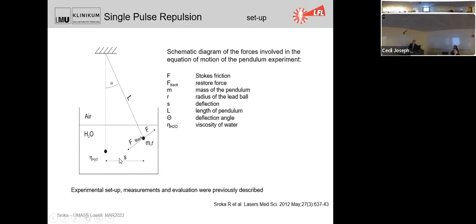So let's go for a little bit on destruction and propulsion. What can be developed there? We can really measure the propulsion. Some years ago, we developed something like a pendulum setup, like this. For the pendulum, we have some iron or some lead here. Then we put the fiber just in front, and based on the force or the impact, the pendulum deviates, and we can measure it and then calculate the effect. We have done this with short pulses and long pulses, and also with different energies, and we can clearly identify that the deviation relates to the laser parameters, and also in combination with the different fiber diameters used clinically, either the 350 micron fiber or the 200 micron fiber.